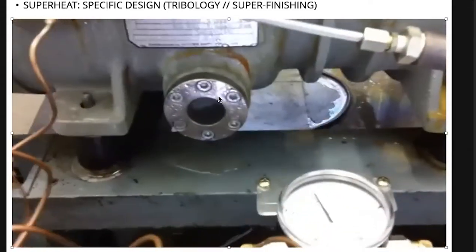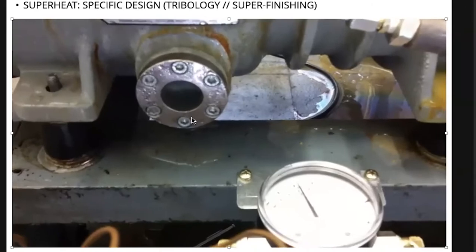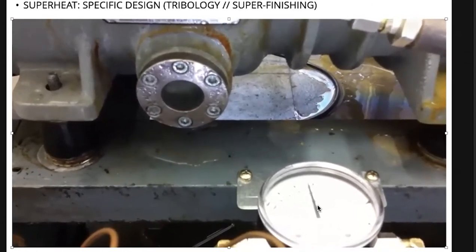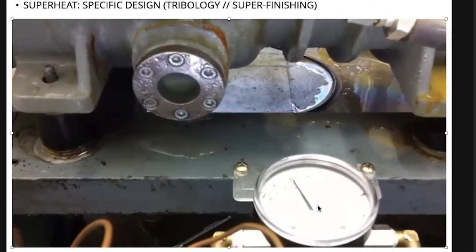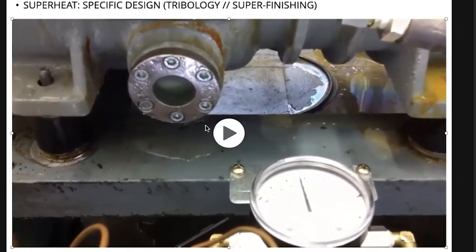You can see oil pressure going down and foaming in the sight glass — typical indication that liquid is coming back. Down and then up. That's when that liquid is making its way into the compressor. Down again and then up again. Why does this happen? Because CO2 is a great detergent, a great cleaner. It washes away the oil film within the compressor and therefore the oil pump is no longer able to develop a correct pressure.